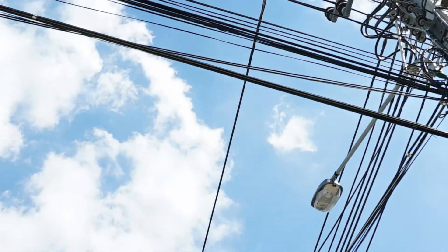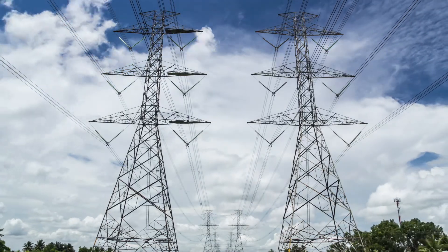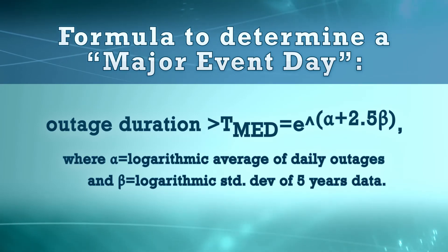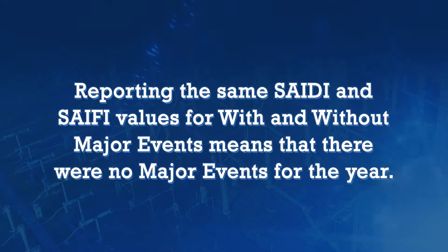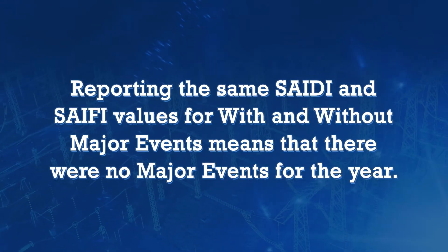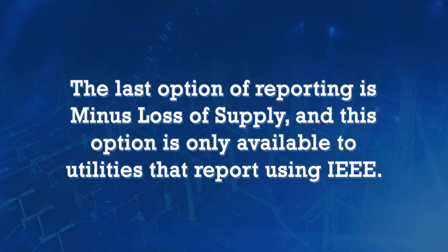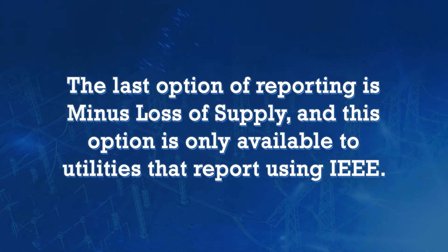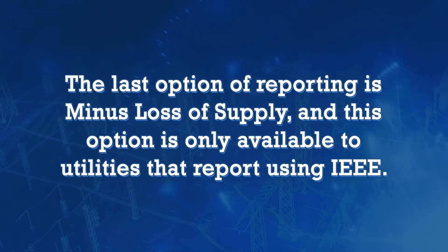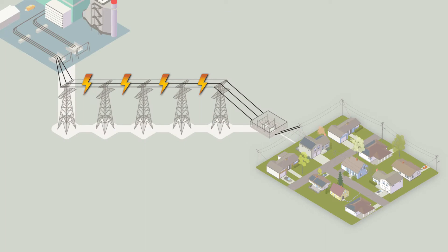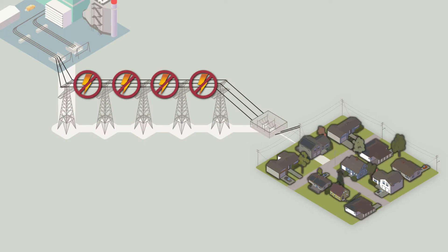Without major events allows utilities to remove some of the outages to give a better picture of normal operations. Any utility using IEEE standards uses a complicated formula to determine whether or not it was a major event day. Reporting the same SAIDI and SAIFI values for with and without major events means that there were no major events for the year. The last option, minus loss of supply, is only available to utilities that report using IEEE, and filters out outage events caused by high voltage transmission lines not being able to supply power. If there are power outages due to loss of supply, this metric will be different than SAIDI and SAIFI with major event days.